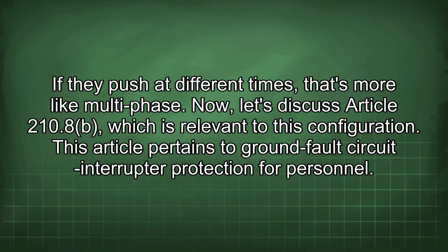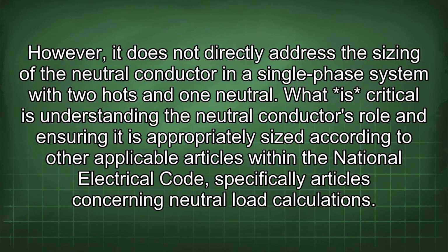Now let's discuss Article 210.8, which is relevant to this configuration. This article pertains to ground fault circuit interrupter protection for personnel. However, it does not directly address the sizing of the neutral conductor in a single-phase system with 2 hots and 1 neutral. What is critical is understanding the neutral conductor's role and ensuring it is appropriately sized according to other applicable articles within the National Electrical Code, specifically articles concerning neutral load calculations.